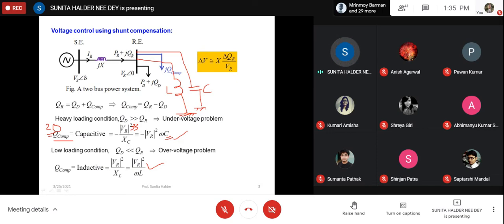Now if you want to buy the capacitor bank in delta, you have to calculate the equivalent delta value of that capacitor - I hope you can calculate that. Generally capacitors are connected in delta, there are several advantages of that, and similarly inductors are generally connected in star. So I hope if you want to calculate the value of capacitor for a particular amount of compensation, you can do it. I shall not give any separate numerical for this.